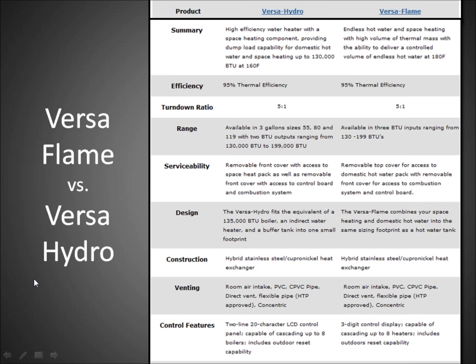Just to give you the VersaFlame versus the Versa Hydro to kind of make the distinction, as you go down, there's a couple areas that I want to point out. In the Versa Hydro, you can see our temperature limitation on the heating circuit is 160, where with the VersaFlame, it's made to go into retrofit. It's made to go into dirty systems, cast iron systems, 180 degrees temperature for standard baseboard for retrofit, and it operates at those high temperatures. And then this just gives you a list of what the differences are and some of the operating characteristics of the system.